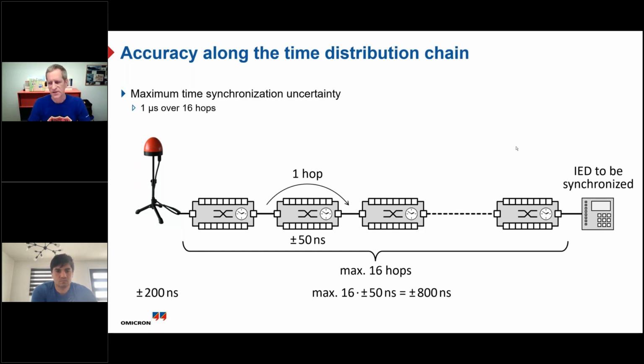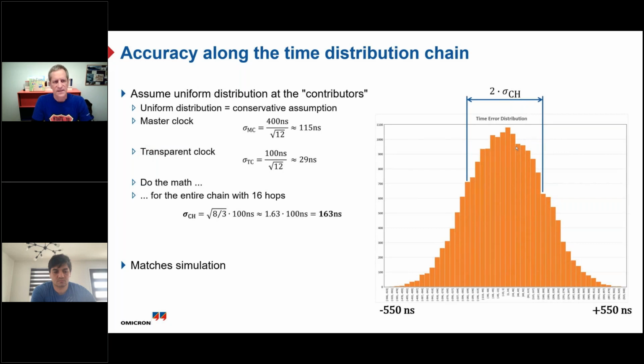And this is how the power system engineers see that, and actually this is a very pessimistic view on the whole thing. So I sat down and calculated that a little bit. I assumed that the uncertainties are uniformly distributed errors in these bands, plus minus 200 nanoseconds or plus minus 50 nanoseconds, and then you come to some standard deviations. And when you count this up for 16 hops, you come to a standard deviation for the whole chain, which is about 160 nanoseconds. And I also did a simulation on that, verified that very nicely. And actually, what we can expect in practice is much better than this 1 microsecond figure.